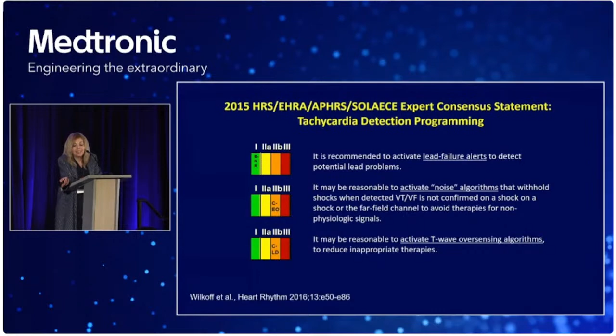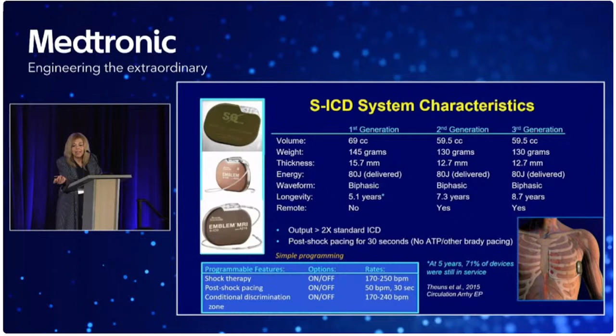Now, the SICD is completely different. You don't have all these different options for programming, right? But you have some, and I think people are probably less aware of these. You just have a shock zone and a conditional zone. You should always program on the conditional zone with this manufacturer's device, because even though you don't get anti-tachycardia pacing, there's no pacing with this device except for a brief post-shock pacing because it's all subcutaneous. There's nothing to do ATP with. You can't do that because that would be painful. But program on the conditional zone because you'll still use discriminators in that zone. And there's some data to support that.